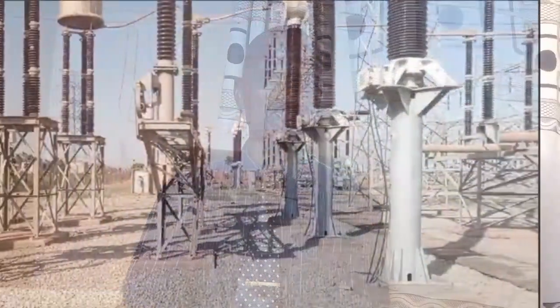Or the person is working and there is a live line or live equipment very close to him, with which accidental contact can be made. So it is that particular circuit that will be tagged. The breaker supplying the live apparatus close to where the work is being done will be tagged, so that if there is any accidental contact by the personnel while doing the work, because conductors can swing, and in swinging they can get in touch with a live line, which will be very dangerous for the person working.